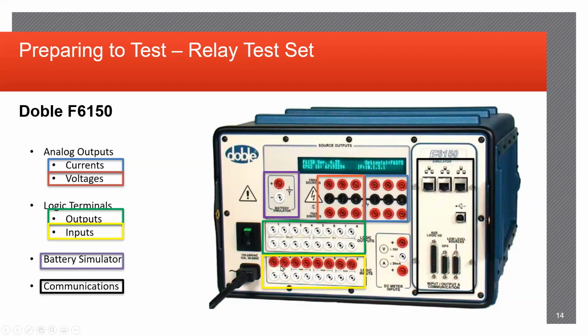Your input side is actually used for the output side of the relay. So if a relay has an output that you're trying to test, you usually plug the low side of that into the high side of this input side and plug the low side back into the reference.